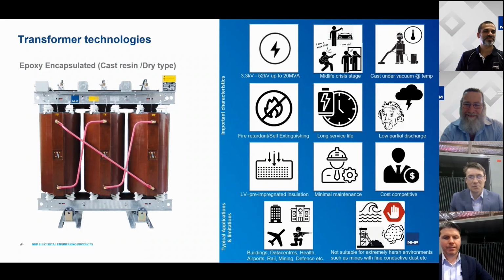Really, I wouldn't put the cast resin transformer straight on the beach. However, there is some very comprehensive testing that cast resin transformers can go through, and we do have it in our range, which is the E3 environmental category. It proves that the transformer can operate under condensation conditions near the seawater. So that's a big tick. Of course, you have to consider protection against corrosion of all the parts, especially the core, and there are different measures that can be taken. So it's possible to install them closer to the water, you just have to provide a good level of protection.